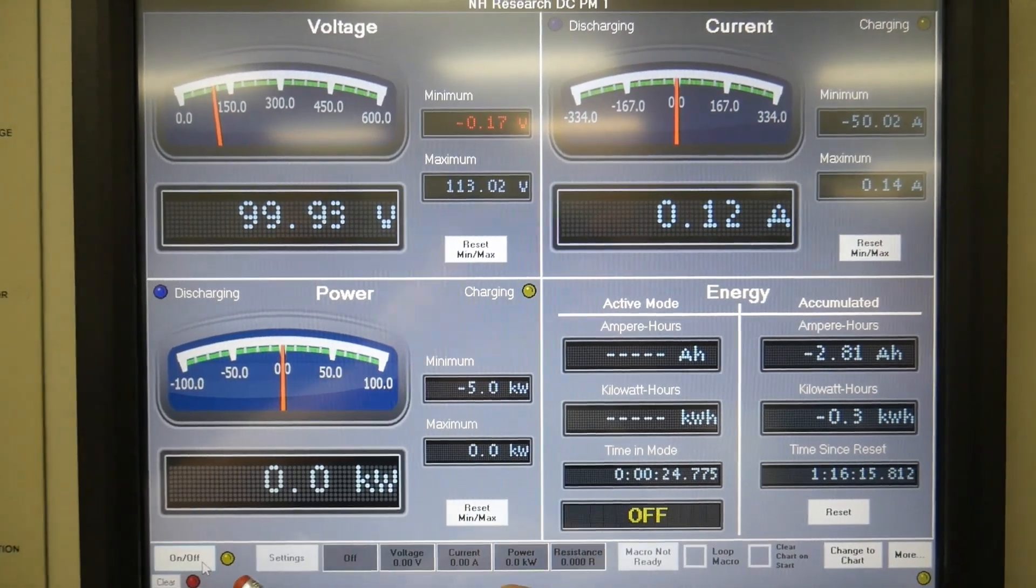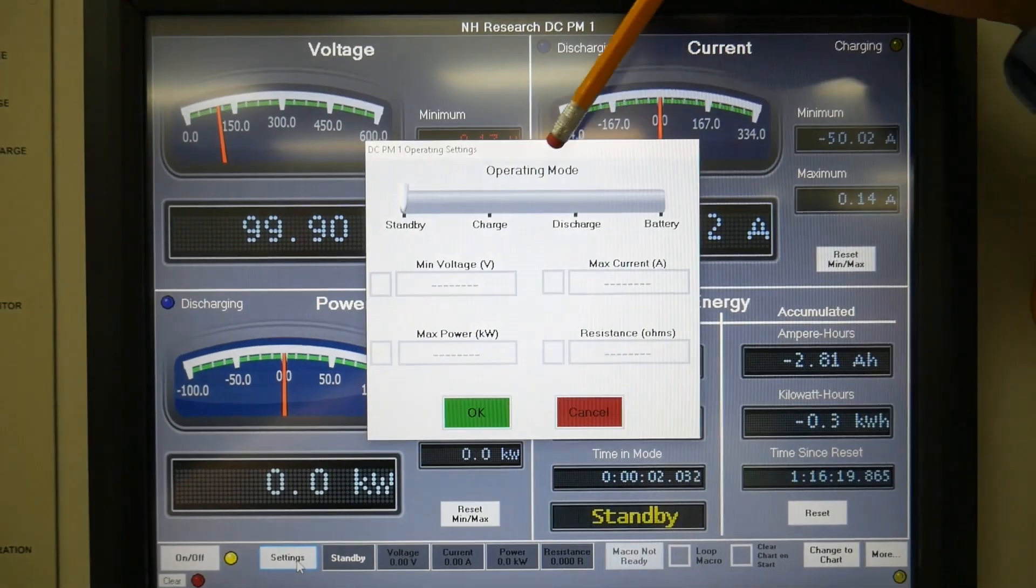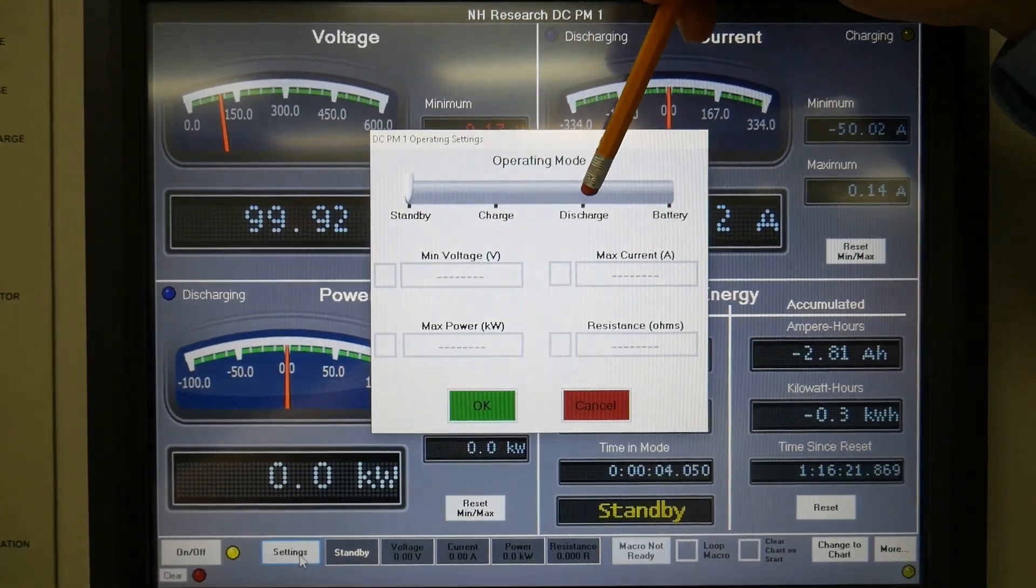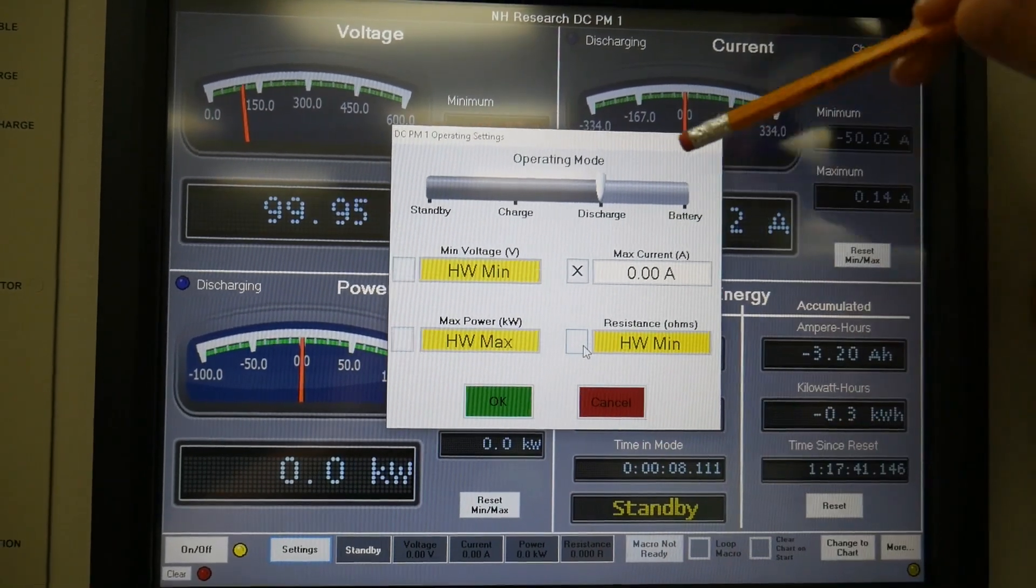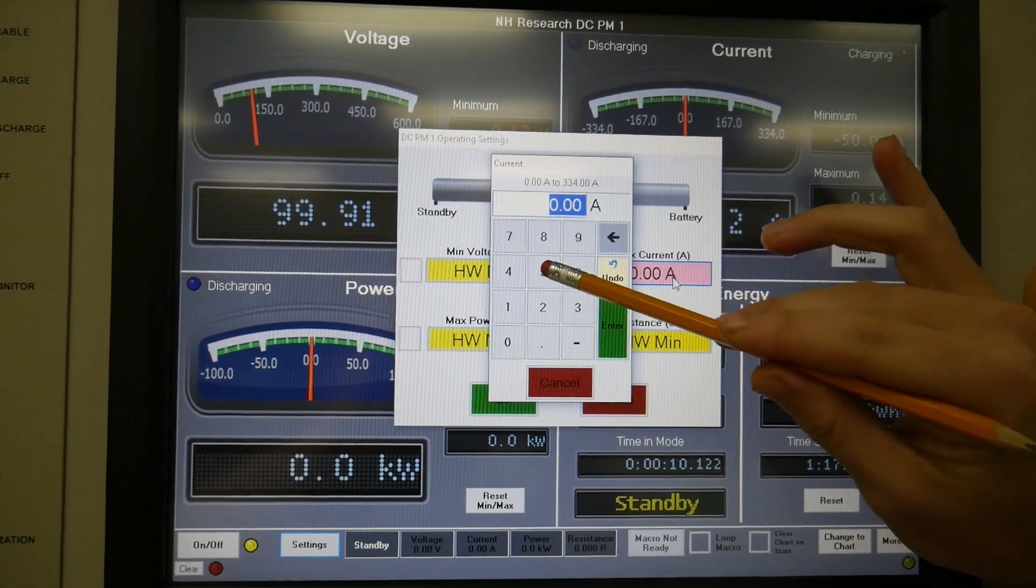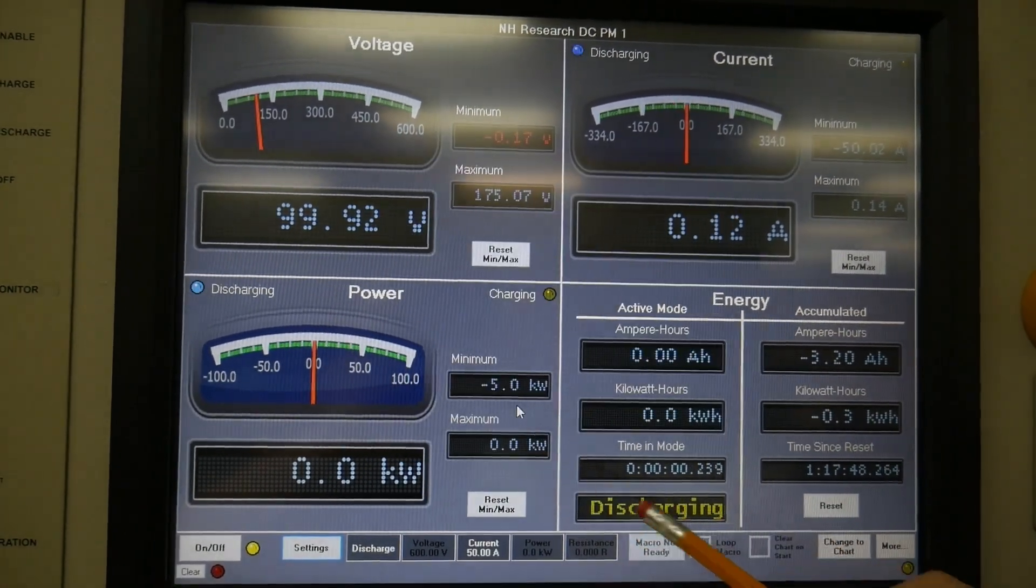To set the unit in discharge mode you would turn it on, hit settings, change the operating mode to discharge. Here we are using the NH-Research 9300 as a DC load drawing 50 amps. Limits will depend on your DUT test and specs.